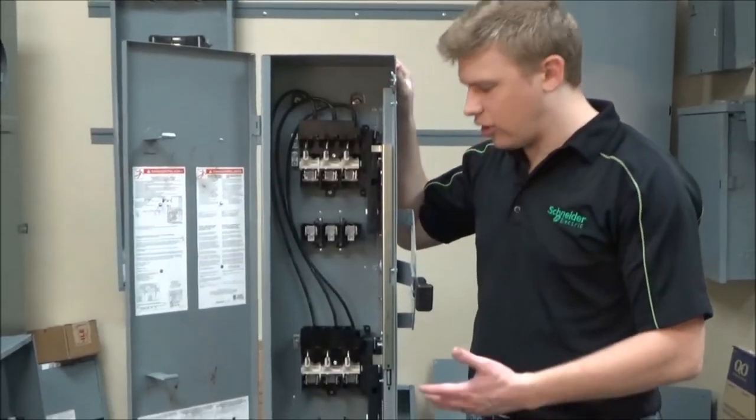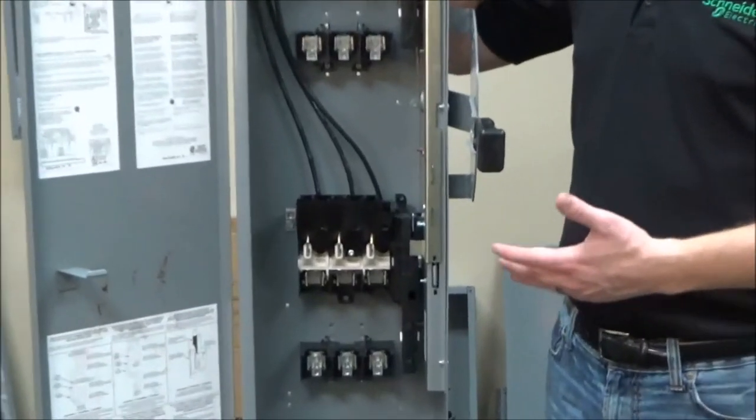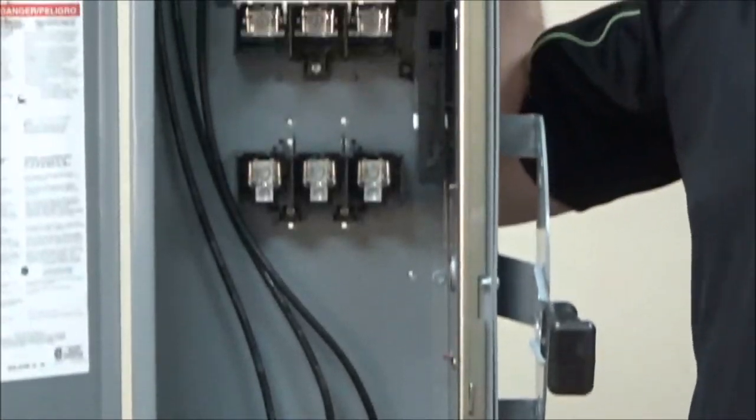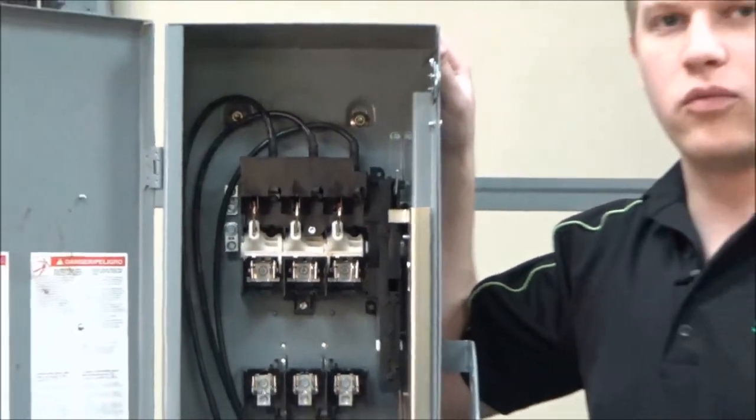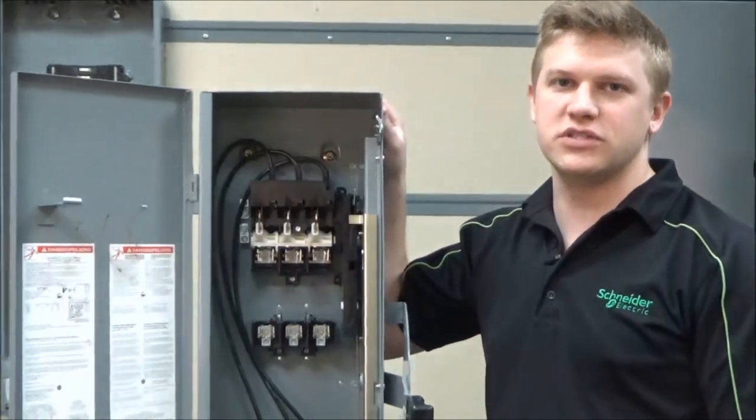Once you have your arc shields installed, you are free to reinstall your fuses. Your switch is now configured for one power source feeding two separate loads.